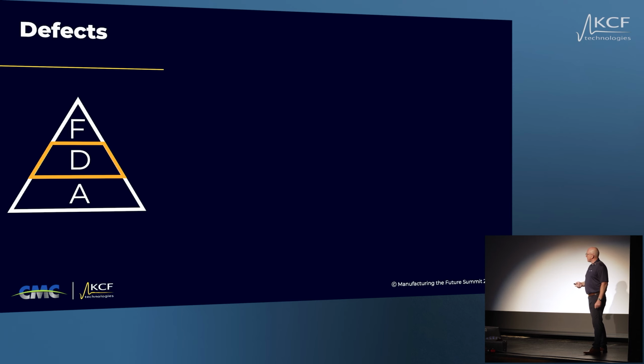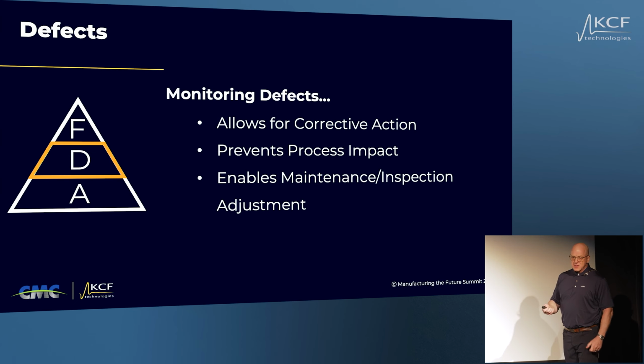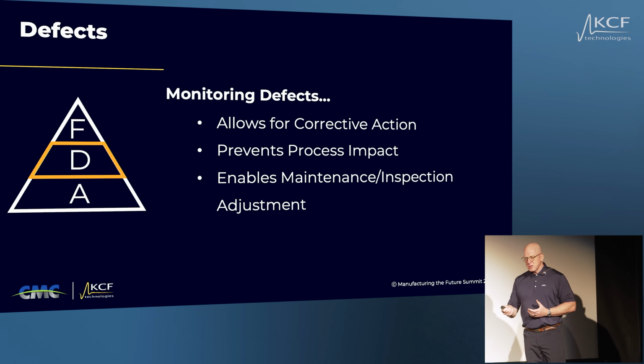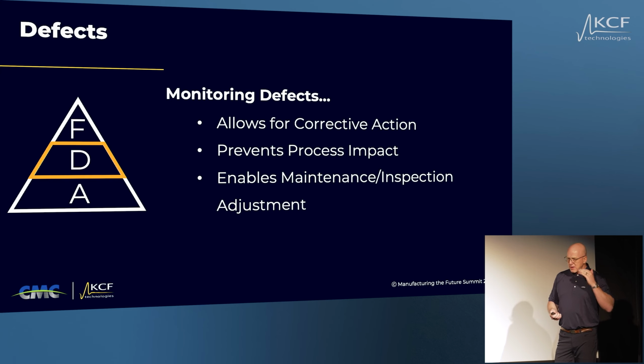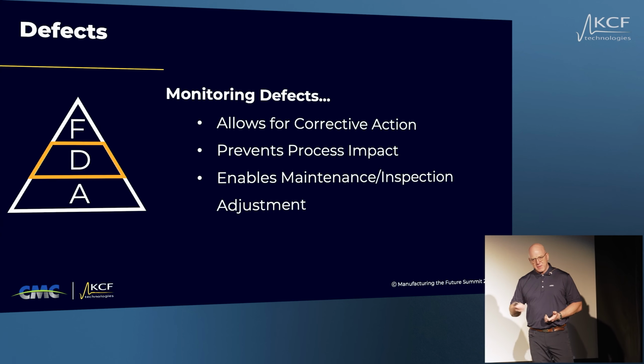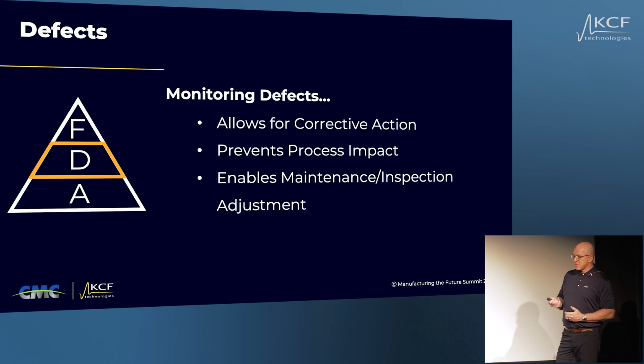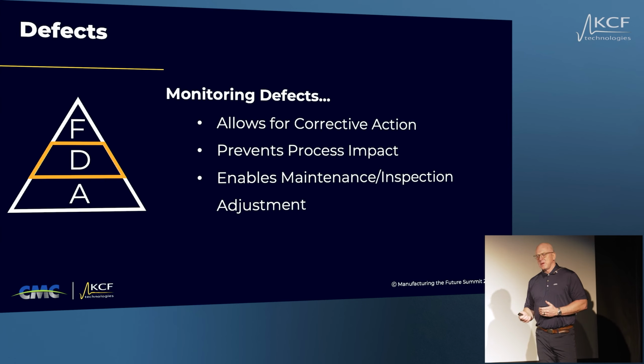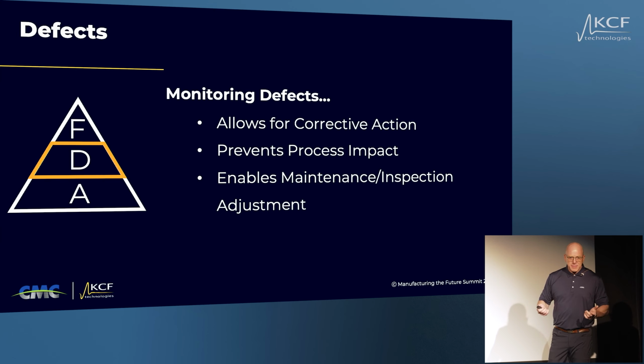So defects, if we investigate and monitor defects, it allows for corrective action. It gives you a bit of time working with the analysts on the solution and looking at the rate of change on either the temperature issue or the vibration issue. You're making data-driven decisions. It prevents process impact. As the examples showed, if you know there's an abnormality or a defect, you can figure out a way to not impact the process. And it can also enable maintenance inspection adjustment. If you've got a piece of kit that has a defect, you might need to change the maintenance program or the inspection program to keep an eye on that or bring some planned maintenance forward.